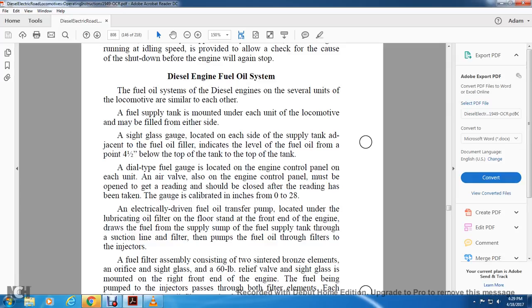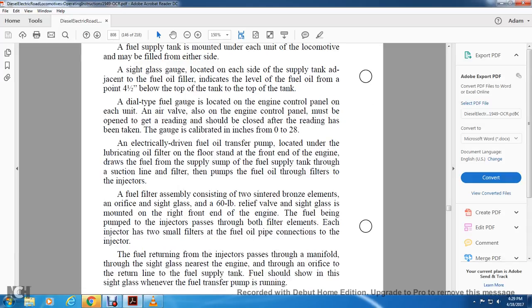A dial type fuel gauge is located on the engine control panel of each unit. The air valve on each engine control panel must be opened to take the reading, and it should be closed after the reading has been taken. The gauge is calibrated in inches from 0 to 28. An electrically driven fuel oil transfer pump is located under the lubricating oil filter. The fuel pump at the front end of the engine draws the fuel oil from the sump of the fuel supply tank through the suction line filter, then pumps the fuel oil through the filters to the injectors.